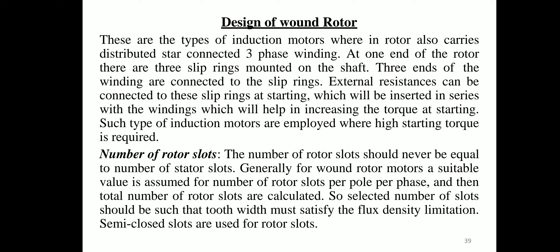Such induction motors are employed where high starting torque is required. The number of rotor slots should never be equal to the number of stator slots. Generally a suitable value is assumed for rotor slots per pole per phase, and total rotor slots are calculated. The selected number of slots must satisfy flux density limitations for tooth width. Semi-closed slots are used for rotor slots.